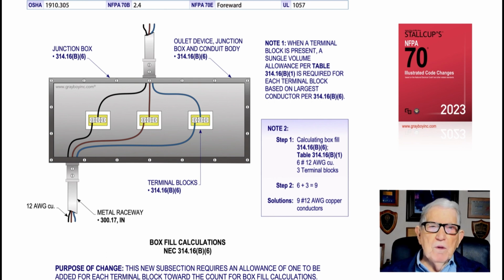When a terminal block is present, a single volume allowance per table 314.16(B)(1) is required for each terminal block based upon the largest conductor that may be present, is basically what it's saying. And that's what this illustration is illustrating: you have to count those terminal blocks in there because they take up fill in the box, and we don't want to overfill and cause heating problems.